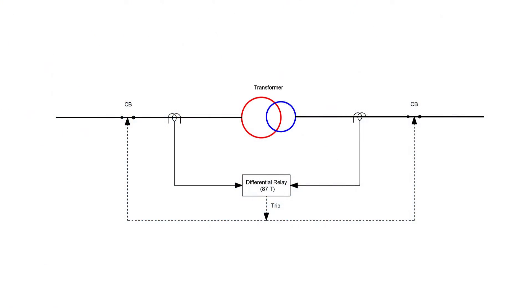The principle of the differential protection scheme is one simple conceptual technique. The differential relay actually compares between the primary current and secondary current of a power transformer. If any unbalance is found between the primary and secondary currents, the relay will actuate and inter-trip both the primary and secondary circuit breakers of the transformer.